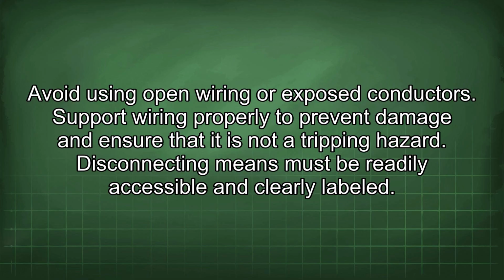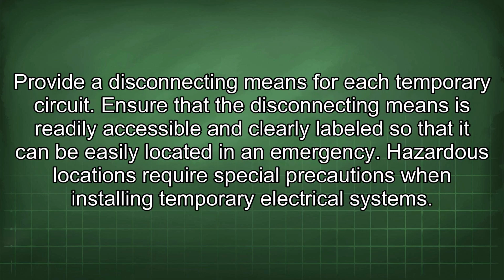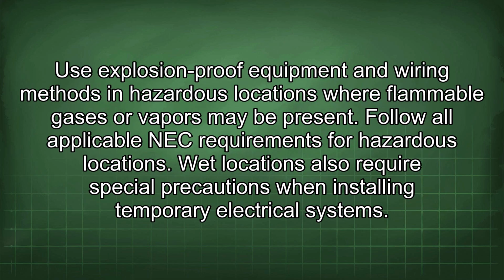Disconnecting means must be readily accessible and clearly labeled. Provide a disconnecting means for each temporary circuit. Ensure that the disconnecting means is readily accessible and clearly labeled so that it can be easily located in an emergency. Hazardous locations require special precautions when installing temporary electrical systems. Use explosion-proof equipment and wiring methods in hazardous locations where flammable gases or vapors may be present. Follow all applicable NEC requirements for hazardous locations.